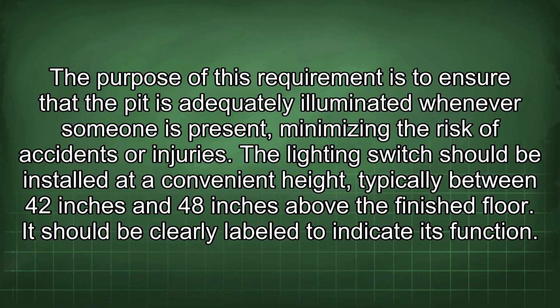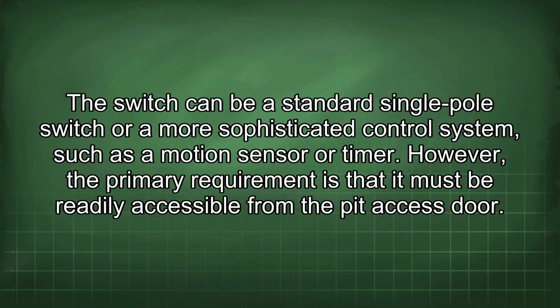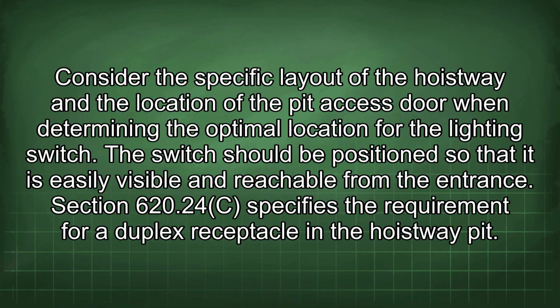The lighting switch should be installed at a convenient height, typically between 42 inches and 48 inches above the finished floor. It should be clearly labeled to indicate its function. The switch can be a standard single-pole switch or a more sophisticated control system such as a motion sensor or timer. However, the primary requirement is that it must be readily accessible from the pit access door. Consider the specific layout of the hoistway and the location of the pit access door when determining the optimal location for the lighting switch. The switch should be positioned so that it is easily visible and reachable from the entrance.